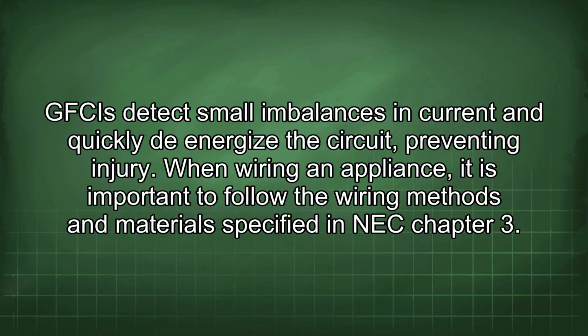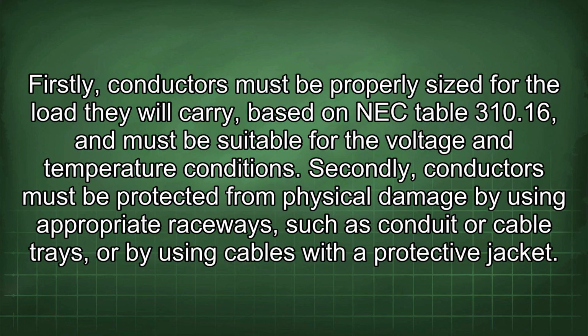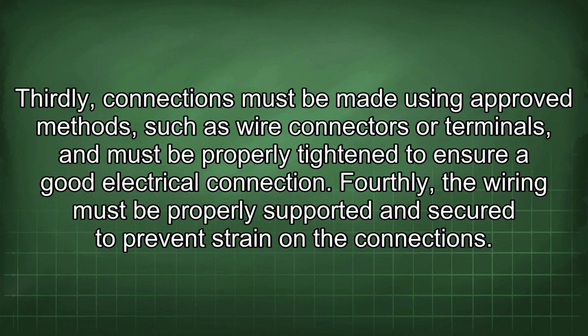When wiring an appliance, it is important to follow the wiring methods and materials specified in NEC Chapter 3. Firstly, conductors must be properly sized for the load they will carry, based on NEC Table 310.16, and must be suitable for the voltage and temperature conditions. Secondly, conductors must be protected from physical damage by using appropriate raceways, such as conduit or cable trays, or by using cables with a protective jacket. Thirdly, connections must be made using approved methods, such as wire connectors or terminals, and must be properly tightened to ensure a good electrical connection.